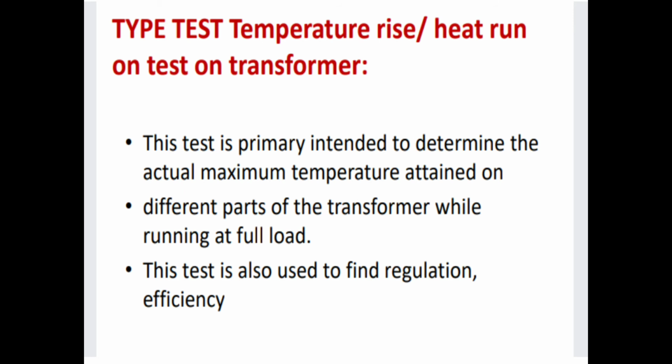So what is the type test, temperature rise, heat run test on a transformer? This test is primarily intended to determine the actual maximum temperature obtained on different parts of the transformer while running at full load. This test is also used to define regulation and efficiency.